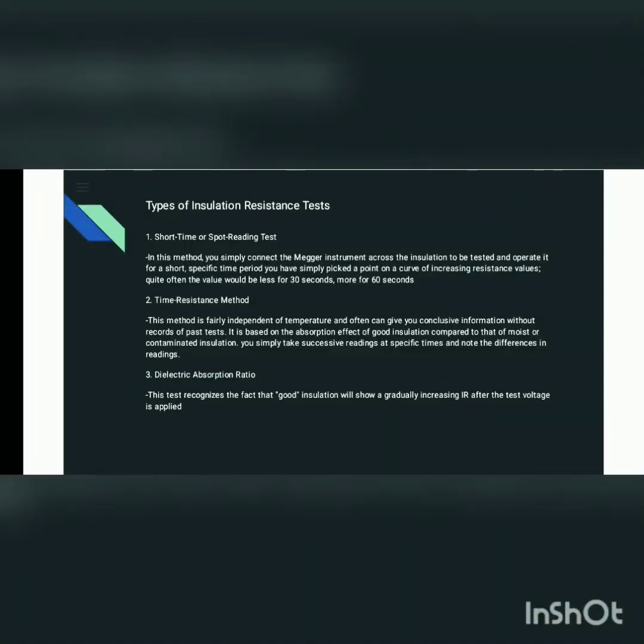There are several types of insulation resistance tests. Number one is the short time or spot reading test. In this method, you simply connect the Megger instrument across the insulation to be tested and operate it for a short, specific time period. You have simply picked a point on a curve of increasing resistance value. Quite often the value will be less for 30 seconds, more for 60 seconds.